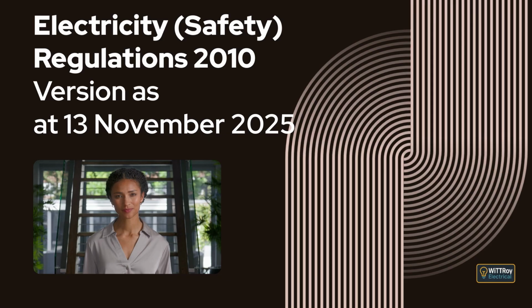Reg 65, requirement for certificate of compliance. This regulation explains that a certificate of compliance must be issued for all general and high-risk prescribed electrical work carried out on an installation or part installation that involves the installation or maintenance of conductors, or the installation or maintenance of fittings connected, or intended to be connected, to those conductors. It then explains that a person who carries out low-risk prescribed electrical work may choose to issue a certificate of compliance, but is not required to do so.